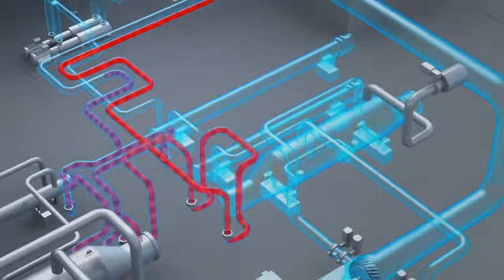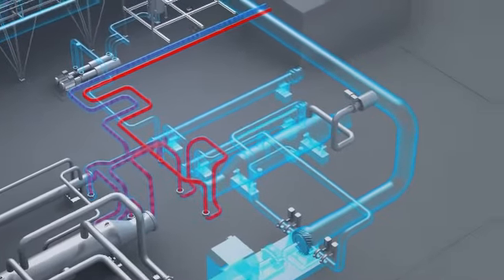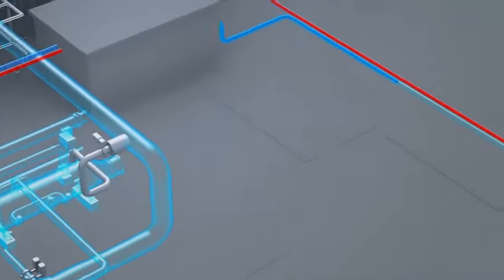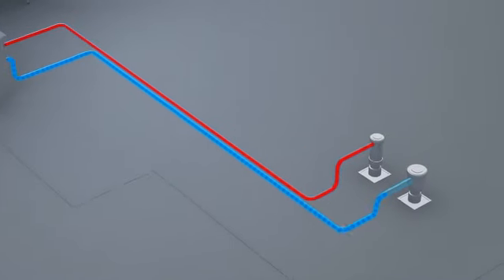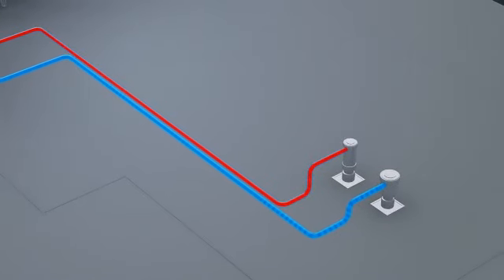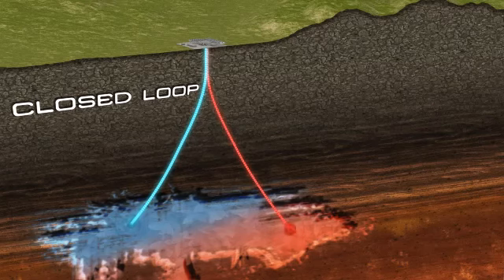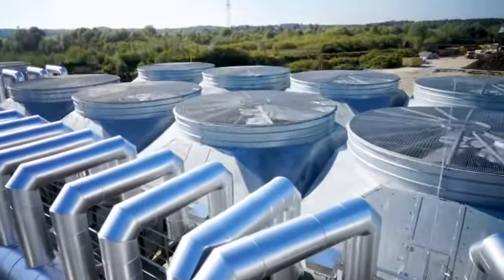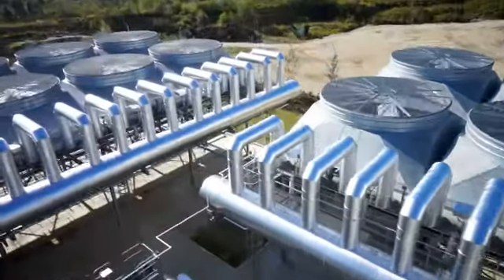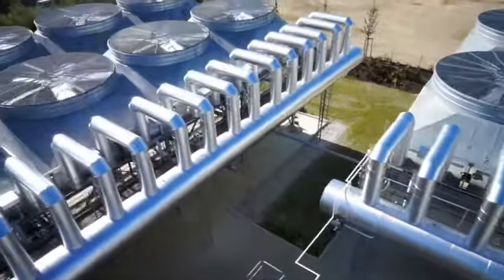The water, cooled by the ORC heat exchangers to a temperature of 50 degrees Celsius, is finally carried back to the aquifer by the injection well. This system thus creates a closed circuit for heat exchange between the geothermal reservoir and the ORC plant, where the entire thermodynamic cycle of the working fluid takes place.